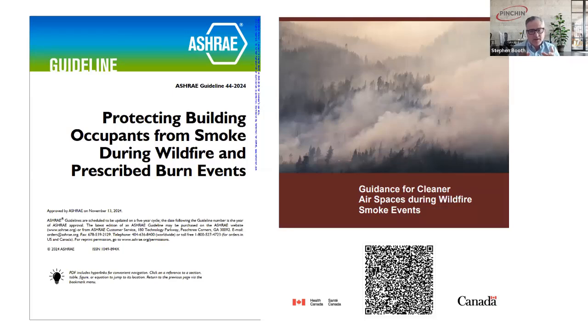The ASHRAE guideline focuses on how to design, operate, and maintain buildings to keep wildfire smoke out and protect occupants—using the building envelope and HVAC system to limit infiltration, upgrading filtration to MERV 13, sealing bypasses, having a smoke readiness plan with clear roles and triggers for smoke mode and recovery steps, and monitoring outdoor and indoor PM 2.5 to adjust ventilation and recirculation during poor conditions. That's the ASHRAE guideline in a nutshell.